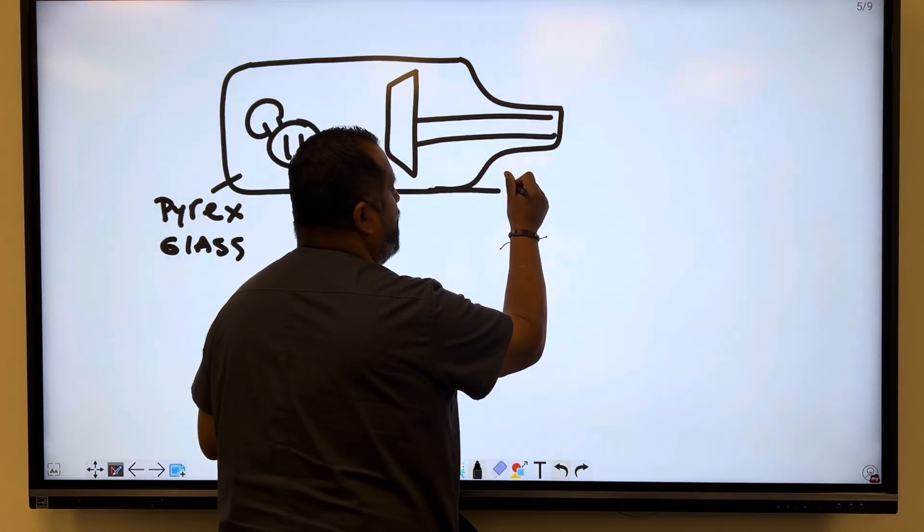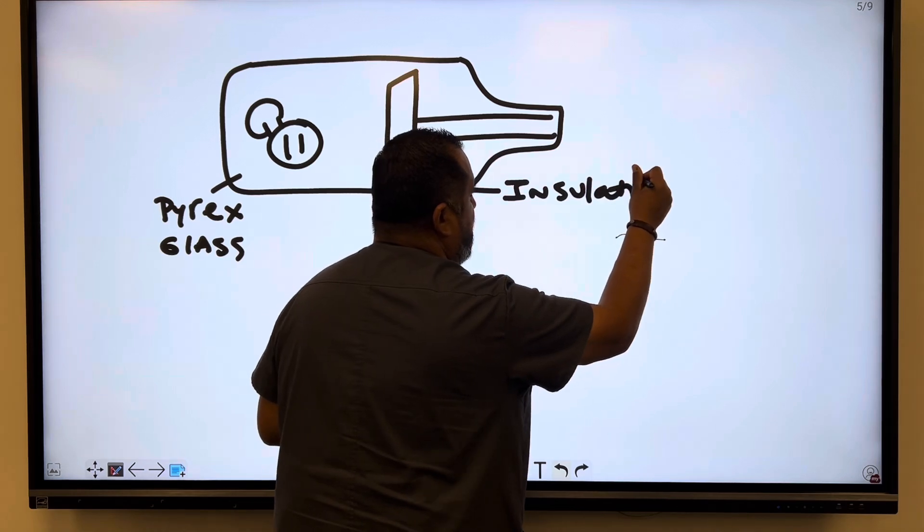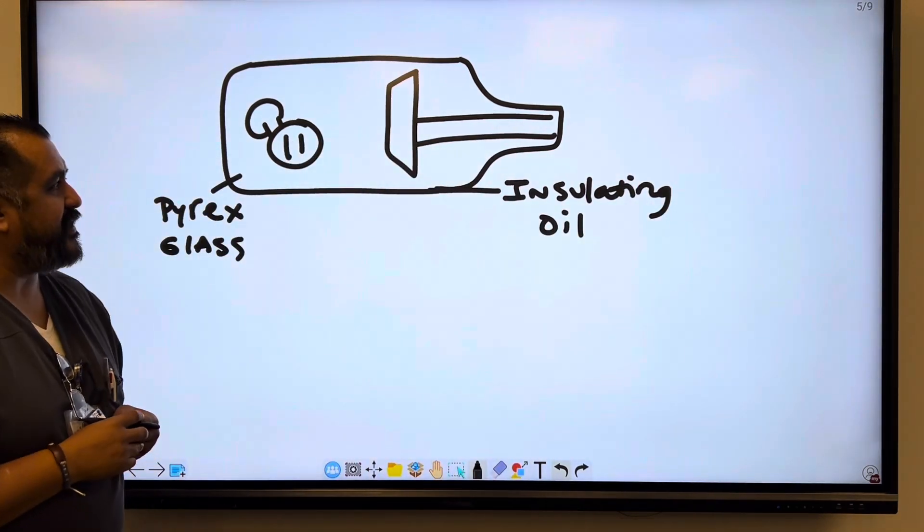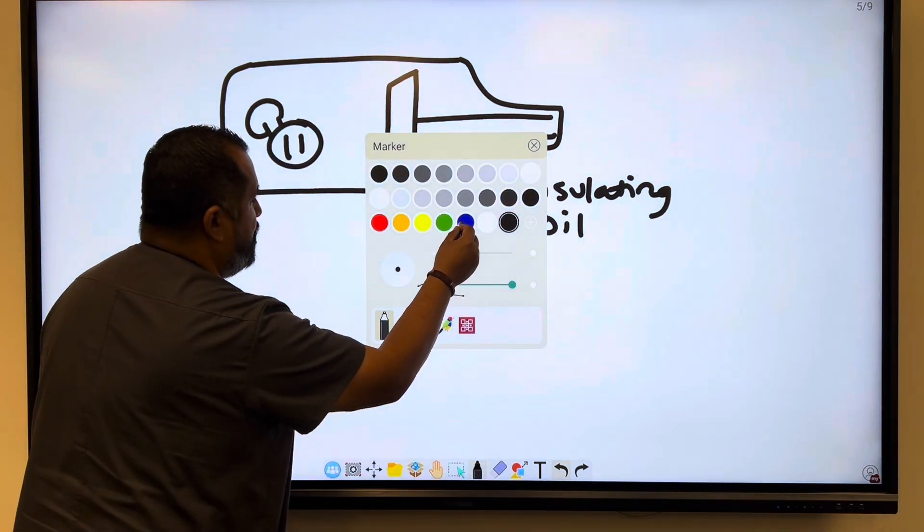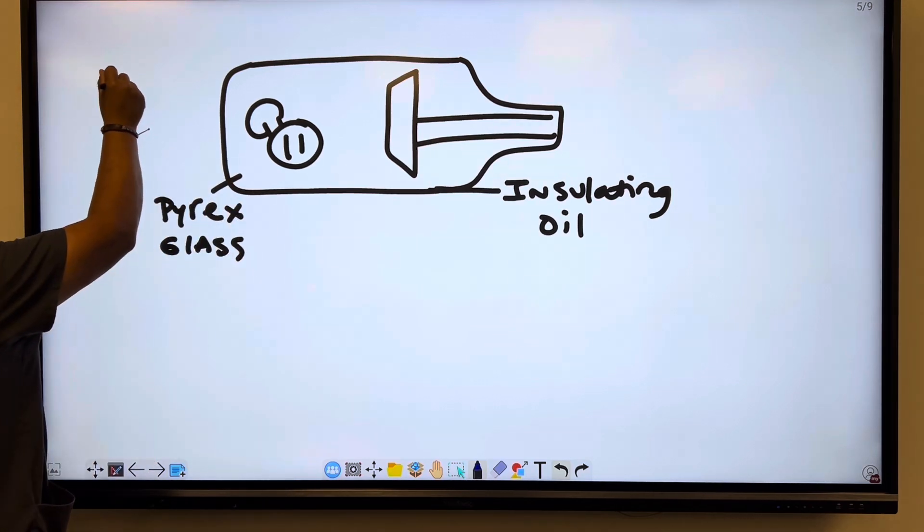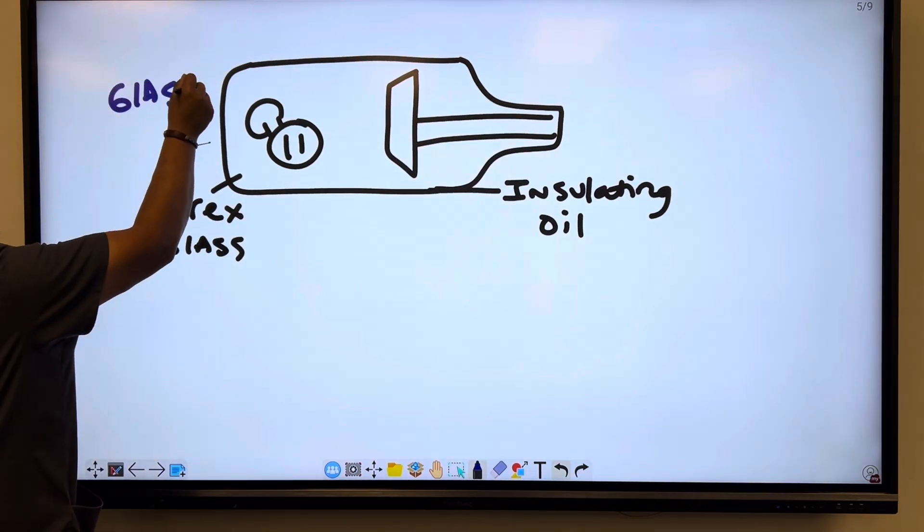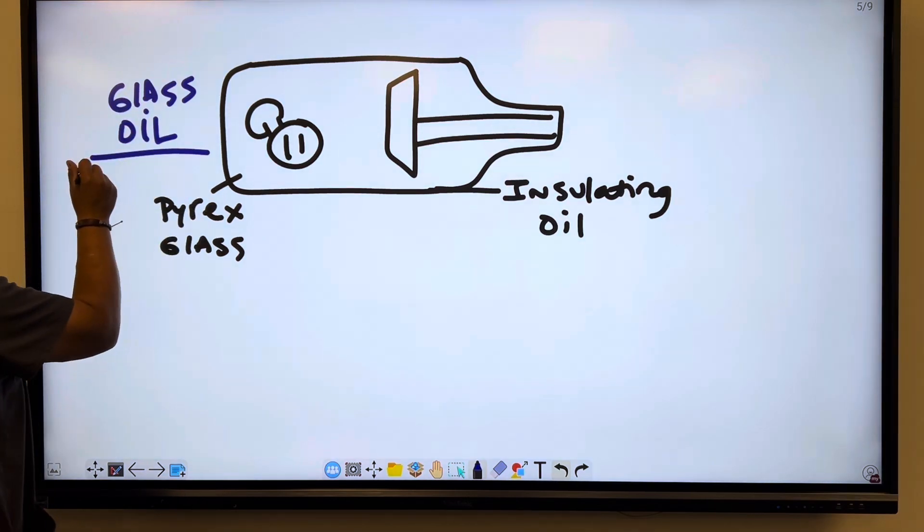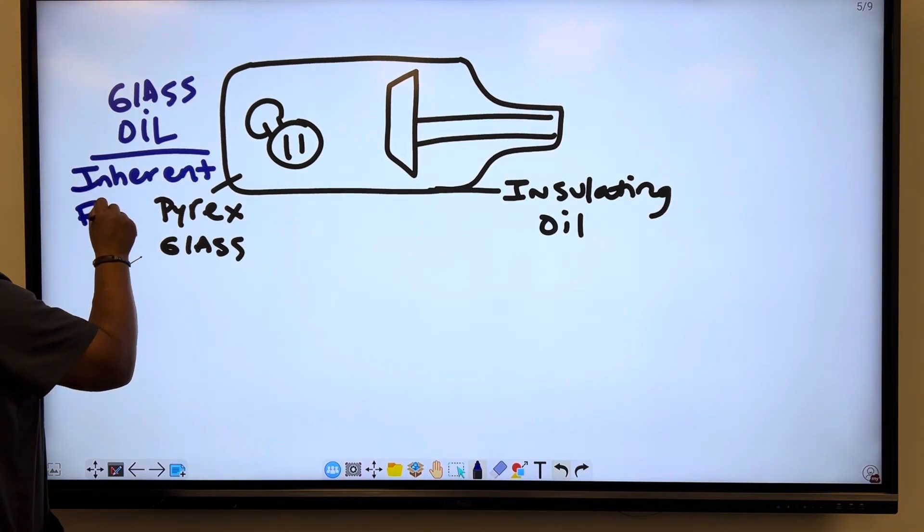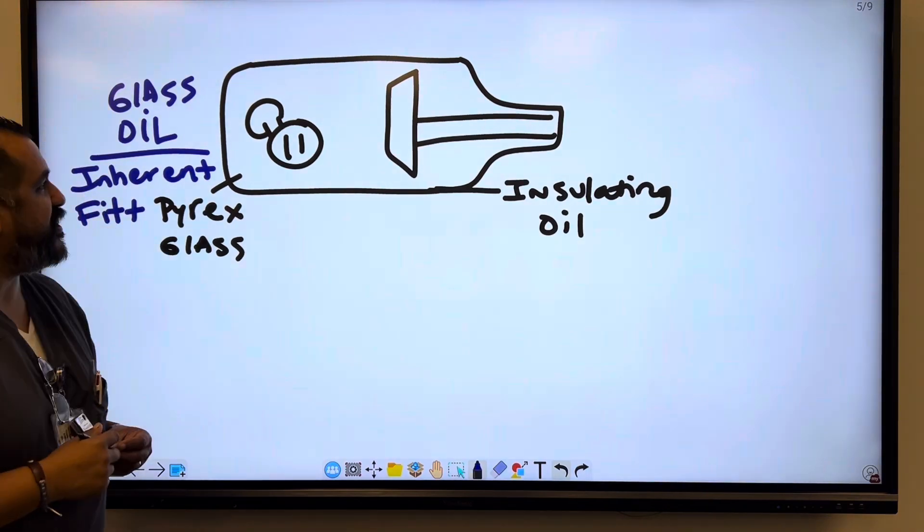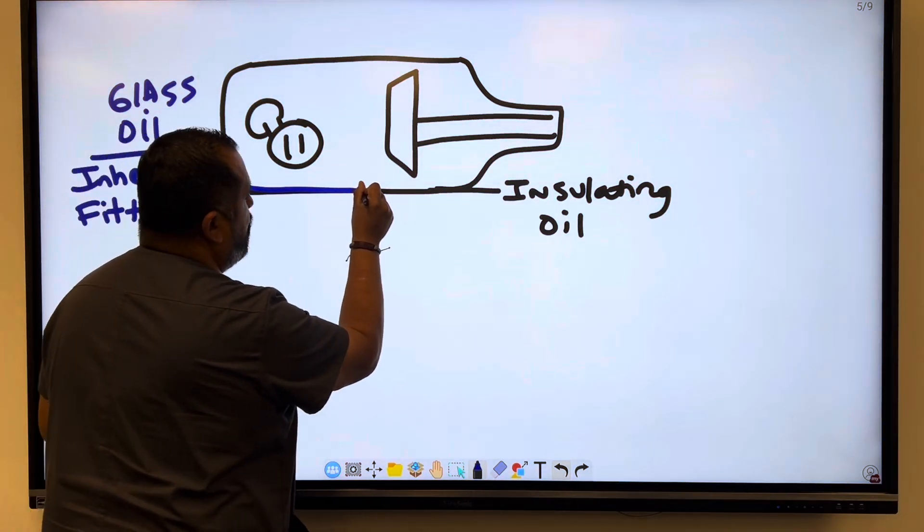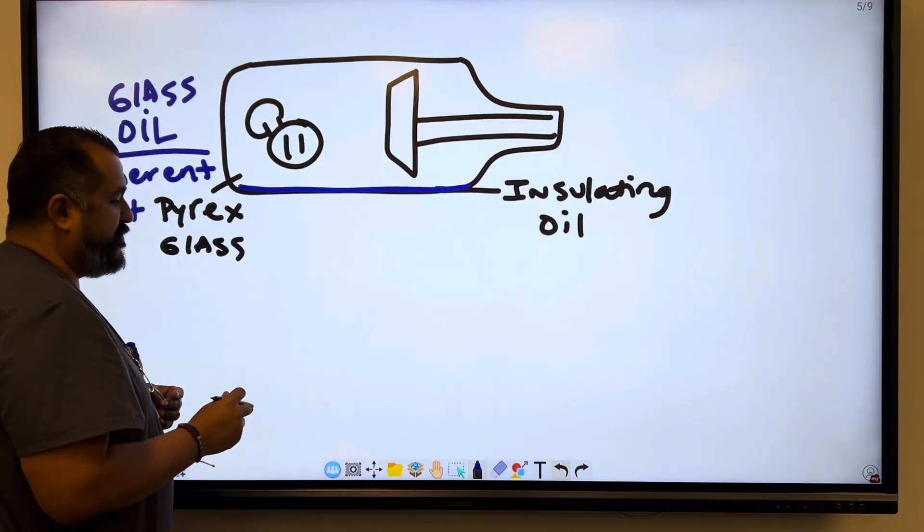Okay, so we have the glass envelope, this is the Pyrex glass, and then there's an insulating oil as well. So the insulating oil, along with the Pyrex glass, is going to be known as inherent filtration. So I'm going to make that blue right here. So the glass and the oil is going to be known as inherent filtration.